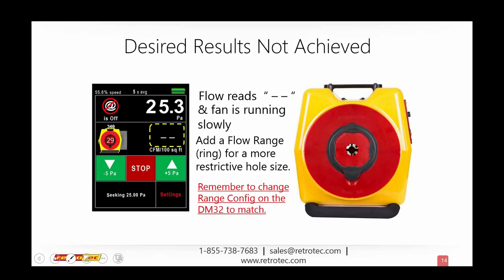So what I want to do is add a flow range or a ring, or even a plug, depending on what model you have. You want a more restrictive hole. The way the gauge works is that it's a calibrated gauge, and it's going to compare an unknown hole to a known hole. That unknown hole is the leakage that's in whatever, the duct or the house or the building or the window, but the known hole is this thing that's right on the front of the fan. So essentially we have brought that space to pressure very easily without moving much air. Without air moving through this hole, we're not getting any readings across our fan or any kind of pressure drop. So we want to add this restrictive hole so that we have a smaller volume of air being concentrated through there so that we can get a reading.